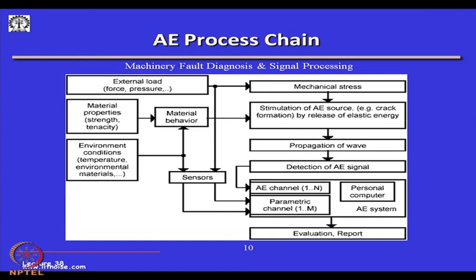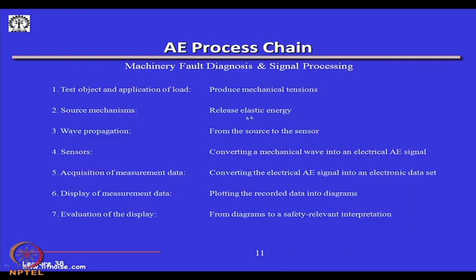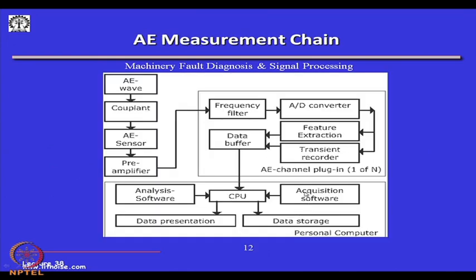Looking at the analog AE process chain: the machine or member is stressed, and because of this there will be a release of elastic energy. This wave propagates, then the acoustic emission signal is detected and recorded with a number of sensors, then put into a personal computer to analyze the signals. Sensors convert the mechanical wave into an electrical signal, and acquisition converts the AE signal into an electronic data set which can be displayed or stored.